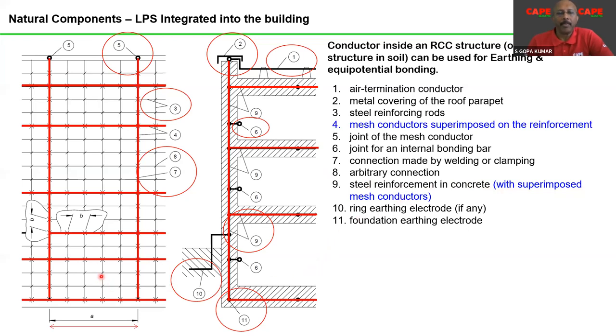So basically, for high-rise buildings and buildings of larger size, separation distance is very difficult to calculate and maintain. Basically, calculation is possible, but maintenance is practically impossible. The best method is to use the naturally available steel as a part of the lightning protection system. For example, in an RCC building, you can put an additional conductor embedded, superimposed in the reinforcement, and this particular conductor will support your structural steel in performing as the whole building as a lightning conductor, for example.